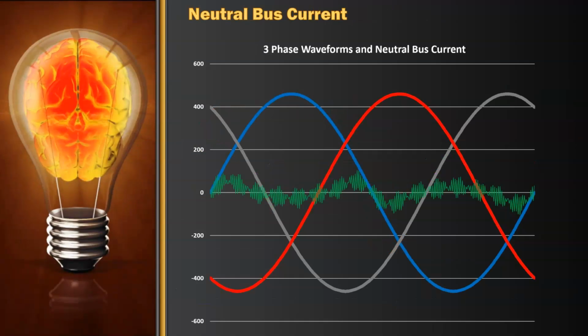But the other thing it does is this is a 3-phase waveform. It increases neutral current, and you can see right there that there's an awful lot of neutral current in this conductor. That's the same 3-phase waveform with the neutral bus and the neutral current in it. And normally in a neutral line, you might have 2 or 3 amps or something like that. On a large circuit, maybe you have 5 amps once in a while. But if you've got 30% harmonic, you might have 70 or 80 amps inside the neutral line. Not good at all. Don't want to see that at all.